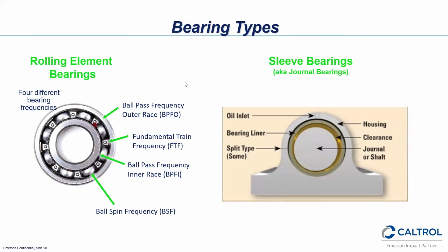I'll go back to the bearings and when I was talking about what types of probes, proximity probes and accelerometers, we use. That's what I was just talking about: sleeve bearings and rolling element bearings. So each one of these components within a bearing has a certain frequency that we can pick out of our spectral data, and anything that happens with the bearing has its own frequency. We can enter these into a library if we know what the bearing number is, and we can program those fault frequencies into our software. And then this is a sleeve bearing, which I was explaining. It's just a shaft that runs in the sleeve and runs on a film of oil.